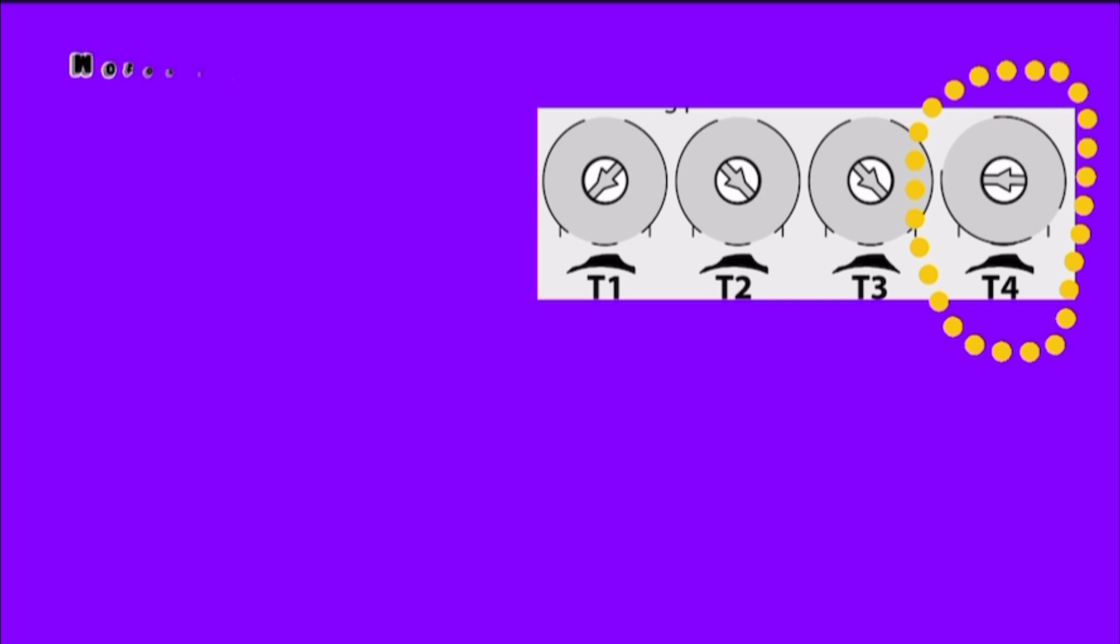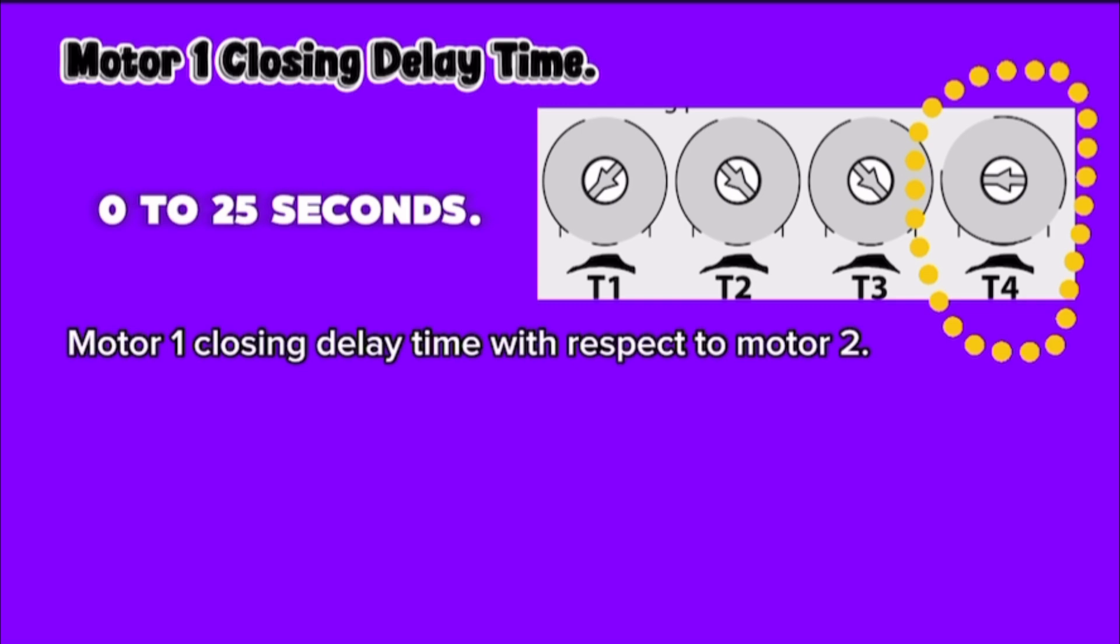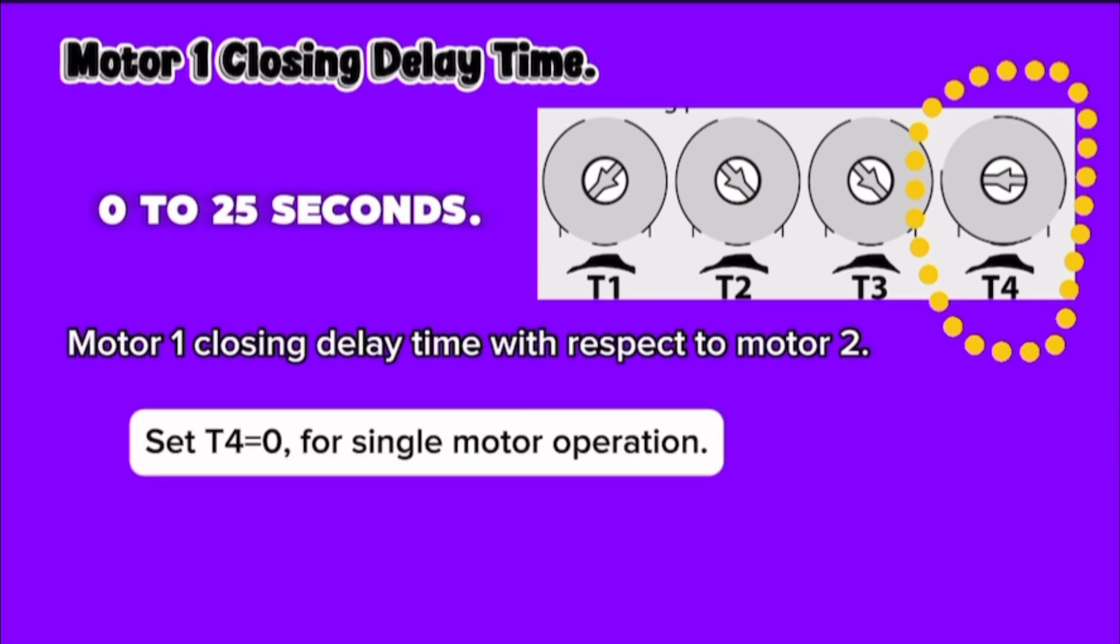T4, motor one closing delay time. The time is in seconds, zero to 25 seconds. Motor one closing delay time with respect to motor two. Set T4 to zero for single motor operation.